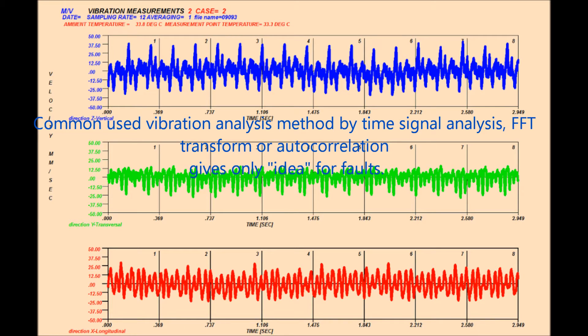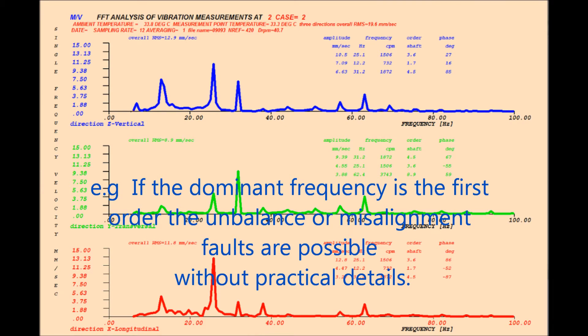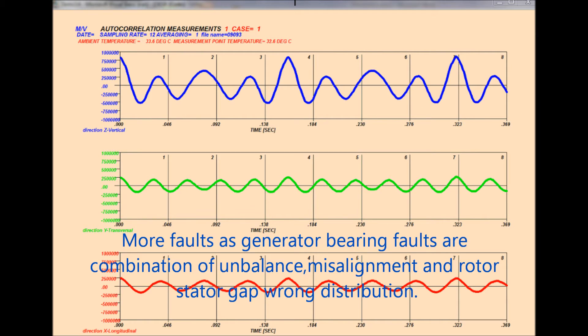Commonly used vibration analysis methods — time signal analysis, FFT transform, or autocorrelation — give only a general idea of faults. For example, if the dominant frequency is the first order, unbalance or misalignment faults are possible, but without practical details. More complex faults such as generator bearing faults are a combination of unbalance, misalignment, and rotor-stator gap wrong distribution.